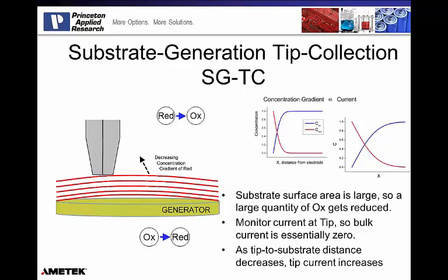So here we're going to use both potentiostats. One potentiostat is going to be connected to the conductor, the sample. One potentiostat is going to be connected to the tip. And I'm going to be able to polarize them independently and dictate what's going to happen. If we think about this, I am really imaging concentration gradients at this point. Don't think about this as imaging of the sites or imaging the sample. In generator collector mode, what I'm really imaging is the electrochemical field or concentration gradient created by the site.